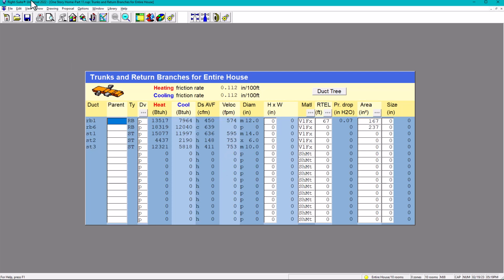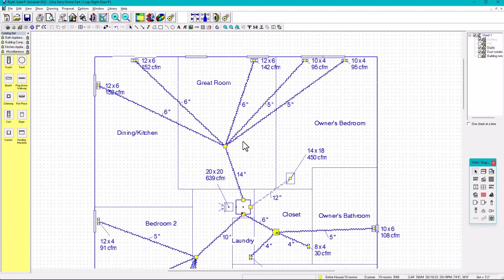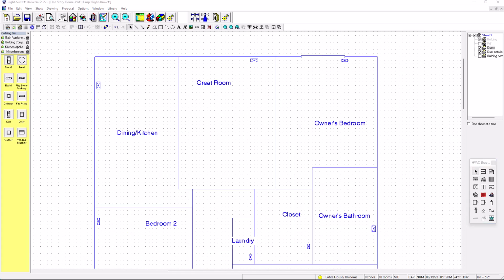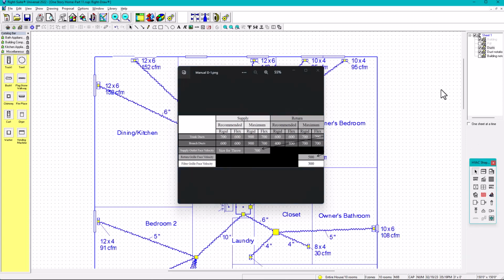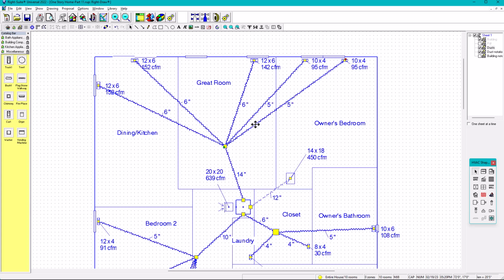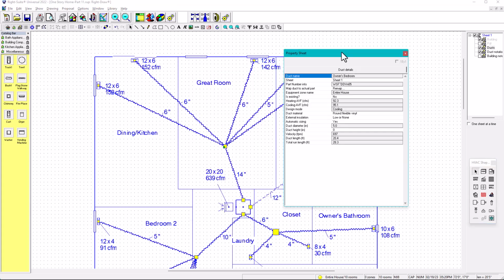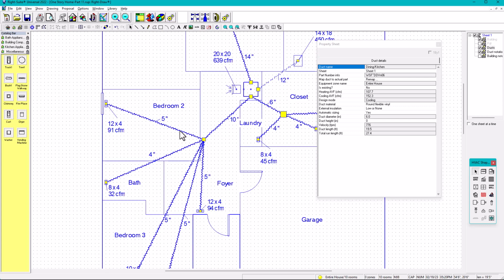So supplies are okay. Now we're going to be checking the branches. For the branches, it says the same thing, 600 to 700. As long as it's around 700, it's okay. What about this branch? This is going to be 697. This is going to be 721. This is going to be 776. That's good, it's around 700. This is going to be 671. Oh, this is so low.